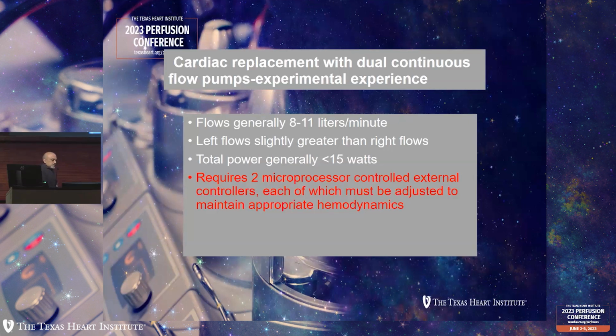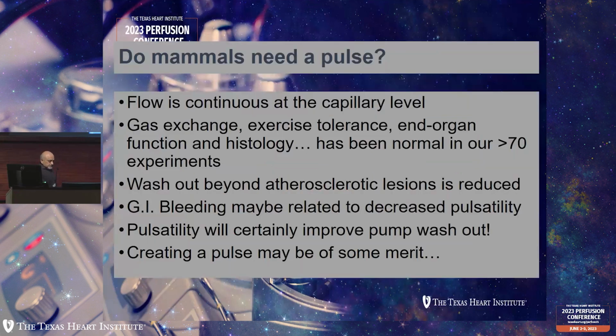So generally flows about 8 to 11 liters per minute. Left flow slightly greater than the right flows. Obviously, we know total power is very low, 15 watts for 2 motors. Remember that. But it required 2 microprocessors. You have 2 different controls, and you have to make sure you're controlling both as needed. So that was another question that everybody would know.